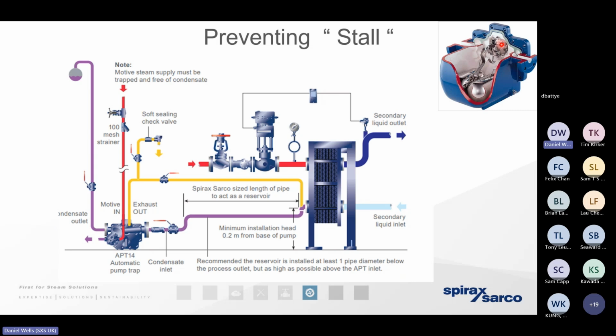But it guarantees two things. It guarantees that we can now size the heat exchanger, so we're condensing the steam at a very low pressure, low temperature, and doing so efficiently. And it guarantees that we can get that high temperature condensate back to the boiler house where we can reuse it as quickly and as efficiently as we possibly can.